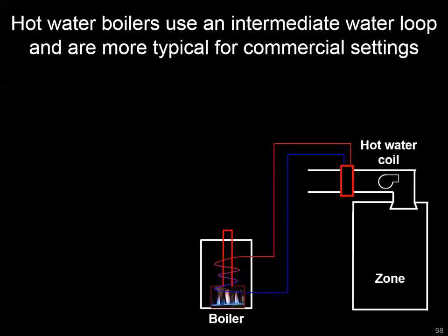The hot water boiler has the same combustion process on one side of the heat exchanger, but on the other side is the liquid hydronic loop. This could be anywhere from 180 degrees down to around 100 degrees in condensing boilers, and that's going to pass heat to some heat exchanger — whether it's a radiator, a coil, or underfloor heating — where you can accomplish convective or conductive heat exchange to address the heat load in your zone from conductive losses in the walls and windows, or from ventilation heating requirements.